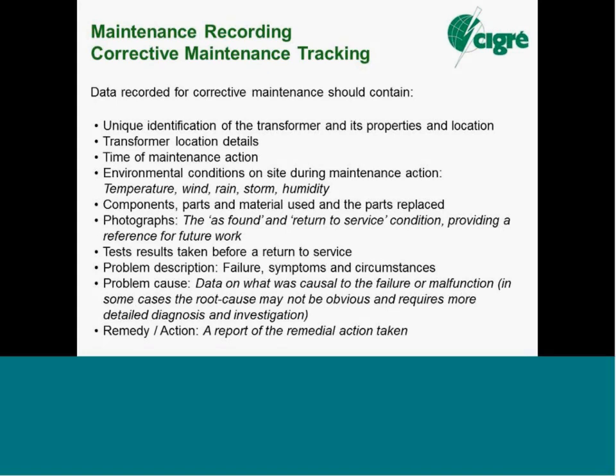Take your basic winding resistance. Copper will have higher resistance with higher temperature. Insulation resistance, the electrical test, the humble megger test of insulation resistance, will drop with an increase in insulation temperature. So you can see why it's important to keep good records to help in assisting just the interpretation of the test.